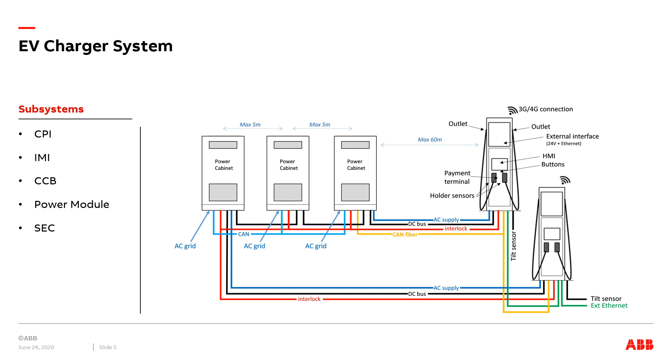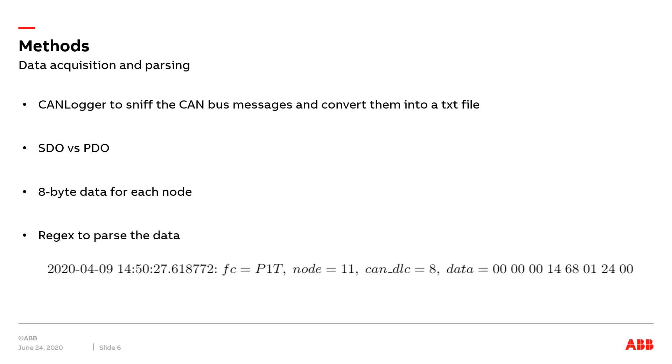The core connection board is in charge of the safety of the cabinet and the control bus distribution. The function of a power module is to supply the desired voltage and current towards the outlet according to the EV's request. The supply equipment control is used for interaction with the user via human machine interface devices and is responsible for system control of HMI devices.